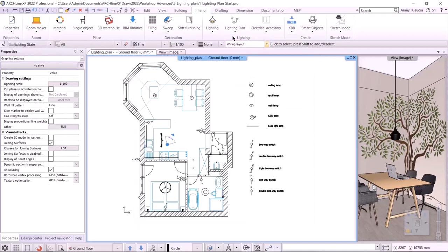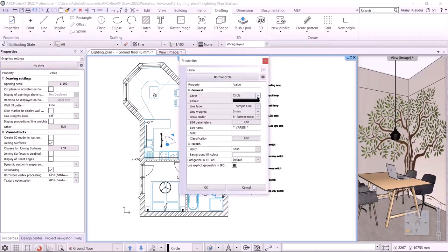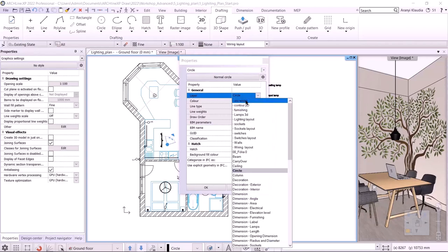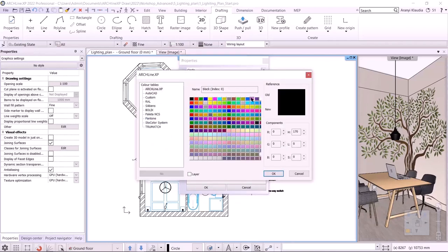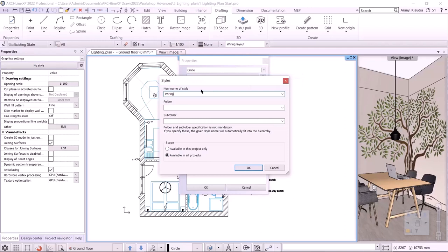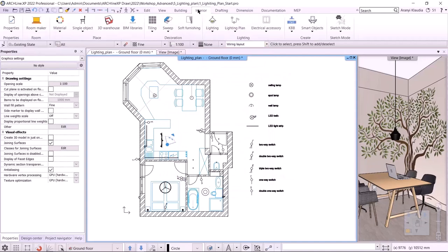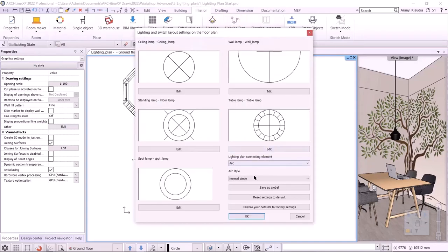To choose from multiple styles, I need to create and save new styles. I click on the drafting tool, select Properties, Circles, and set its properties. The layer it will be placed on is the arc wiring that I have created beforehand. The color should be pink as you could see in the finished PDF. The line weight should be 0.5 mm. With a click on the cogwheel icon, I save it as a new style — the name should be wiring layout. I go back to the interior lighting plan settings and from the list I select the new style. Here we can also reset the default settings if needed.